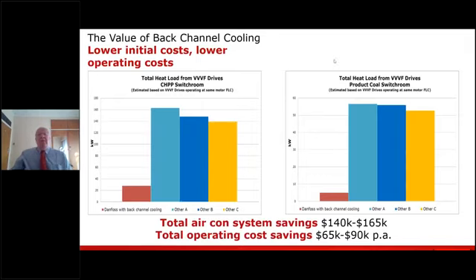Now, when we showed this and used the back channel cooling as a value proposition, you could all of a sudden see how the heat going into the switch room had reduced substantially. And when this was all put together, it was found that the total air conditioning savings, that was the air conditioners themselves, would give them a cost saving of between $140,000 to $165,000 for all the switch rooms. The reason it's 140 to 165 is that at the time we weren't sure which air conditioning units they were going to use, because they didn't know themselves.